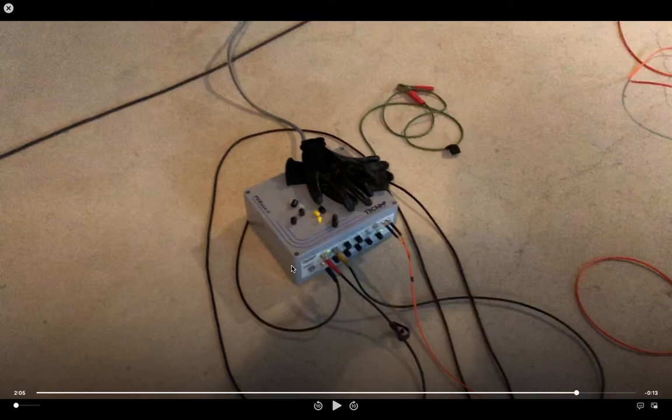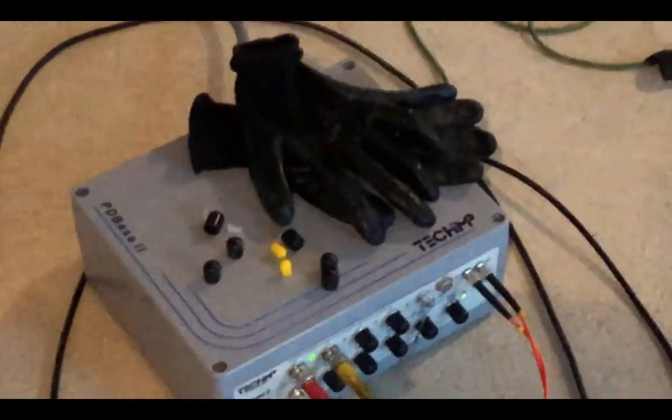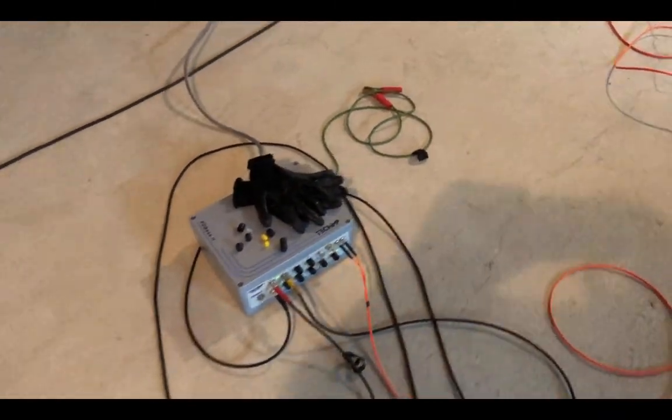PD Base 2 is a very powerful test set. It is essentially an oscilloscope, but it is an oscilloscope which has ultra-wide bandwidth from 16 kilohertz all the way up to 48 megahertz. And you can use it in a lab or, as you can see, in the field. With this unit you can test cables, rotary machines like generators and motors, you can also test GIS medium voltage equipment or transformers. It's just the type of sensor that changes.